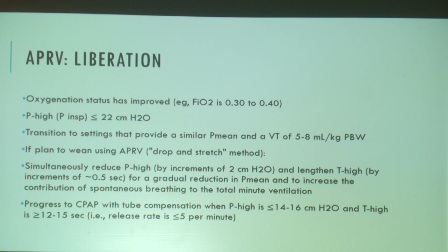And so eventually you'll get to a point where you're essentially on a straight CPAP, where you have a set pressure level, and then they're still taking those spontaneous breaths on top of that CPAP level. And that would be when you're at a P high of about 14 to 16 and a time high of 12 to 15 seconds. Or T high can be called infinity, and then you have achieved CPAP. Yes, yep. There's no infinity setting though.